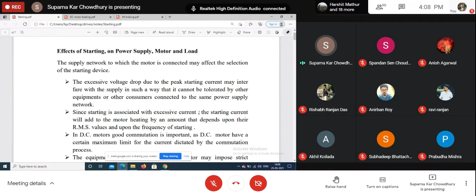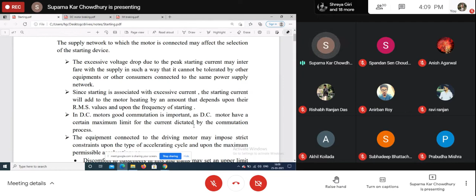Now DC motor has a moving contact, the commutator and the brush, and however well the motor is maintained, there will be sparking because it is a moving contact. In commutator segments, you know, we have copper segments insulated by thin mica separators. Now there is a voltage that the mica separator can withstand. If the current increases, there is a possibility of flashover from one commutator segment to another.